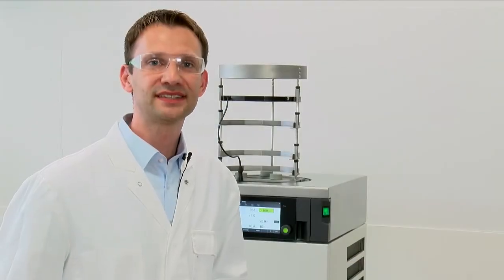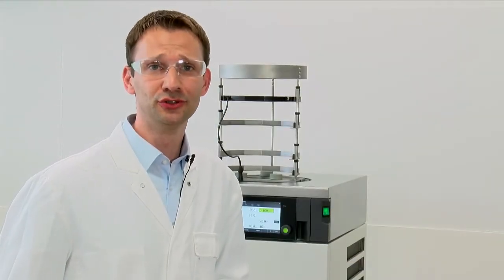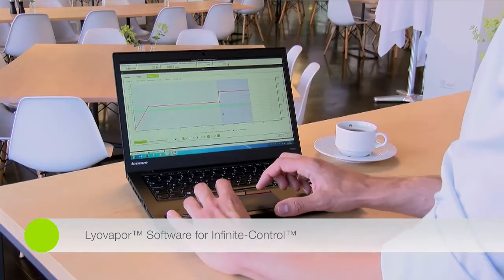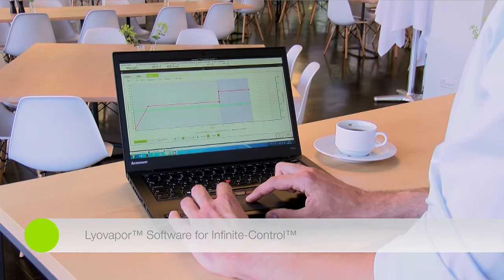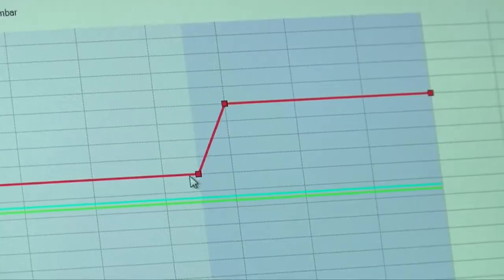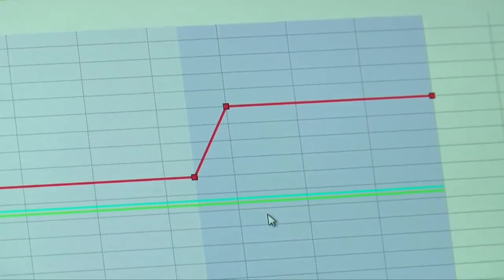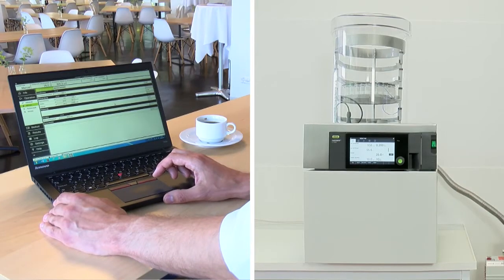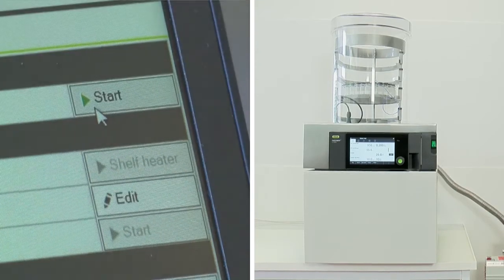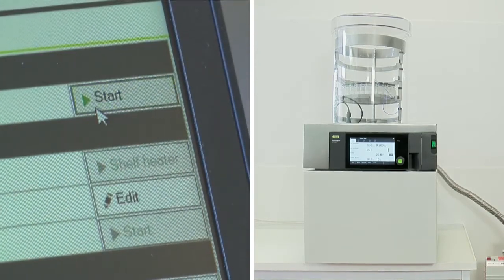But what makes the Lyovapor L200 truly unique is the combination with the Lyovapor software. With the software, it's very easy to program automatic freeze drying cycles to transfer the cycles to the instrument and to start conditioning of the instrument from your office or when having another cup of coffee in the morning.